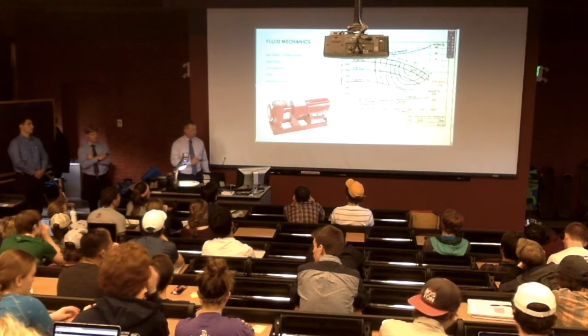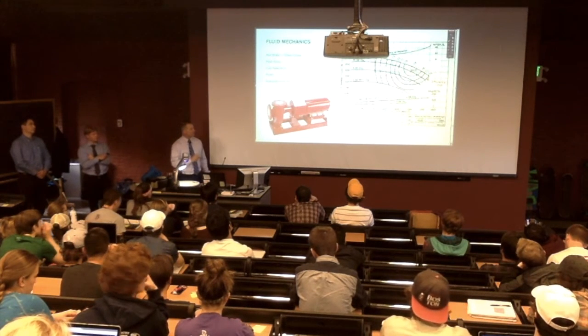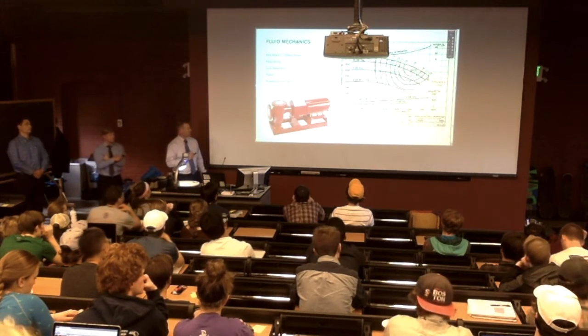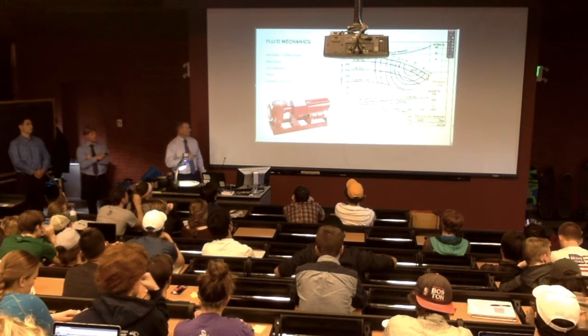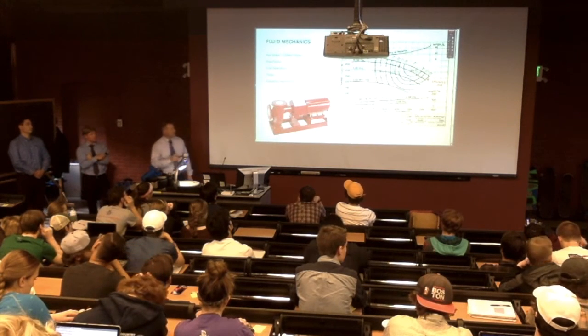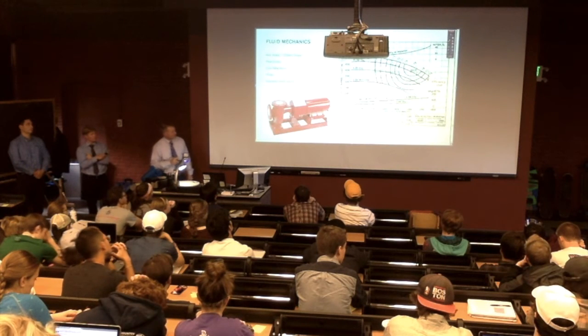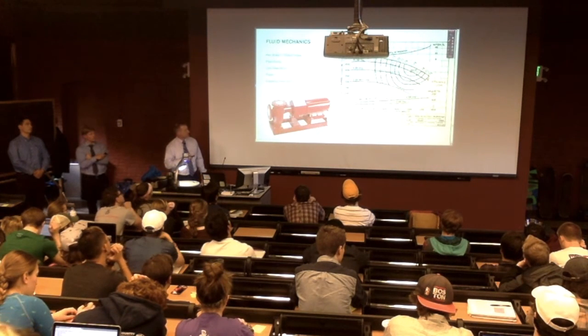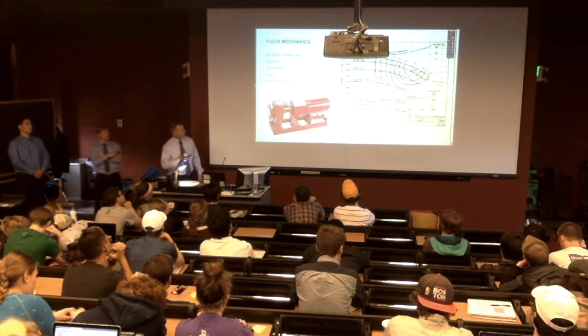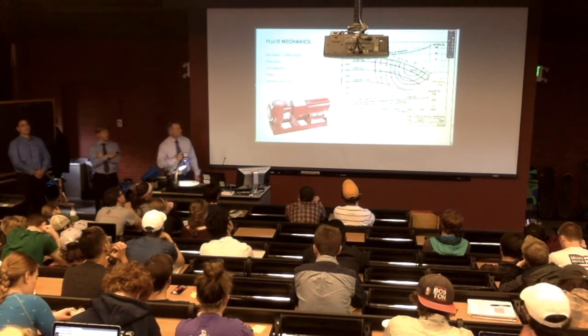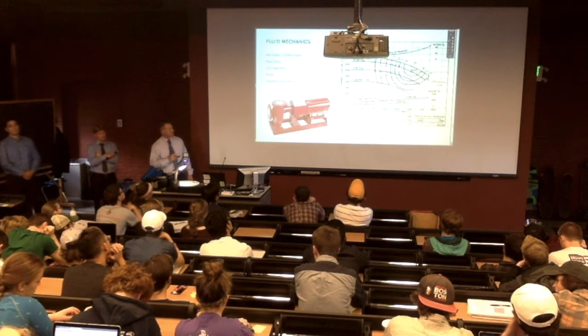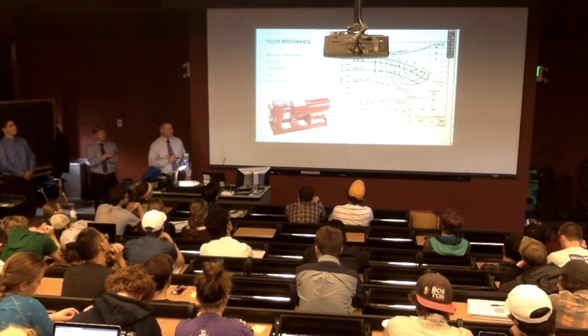This is an example of a pump curve right here. There's a picture of a pump. You can see the water comes in this end, it goes out that end. It's called an end suction pump. This is a pump where, if you looked at it at 1,000 gallons per minute at 450 feet of head, that's the optimal point to select the pump. It's the highest efficiency. Generally, we design these systems that way.